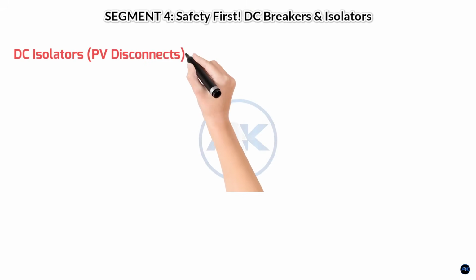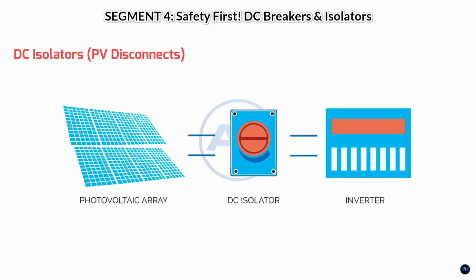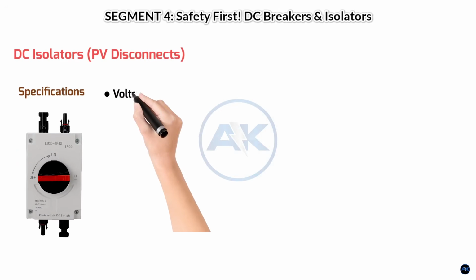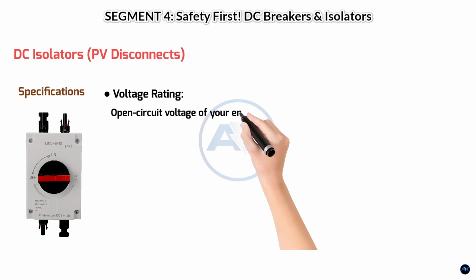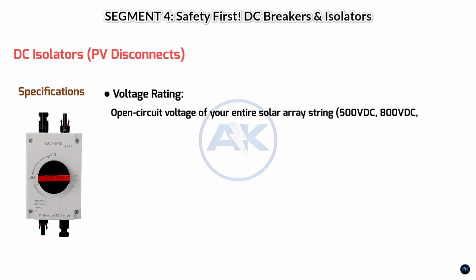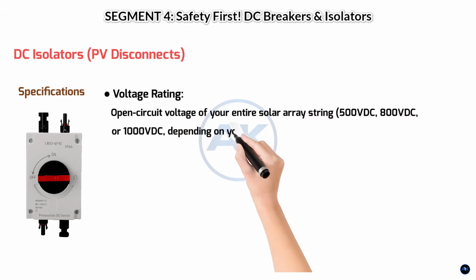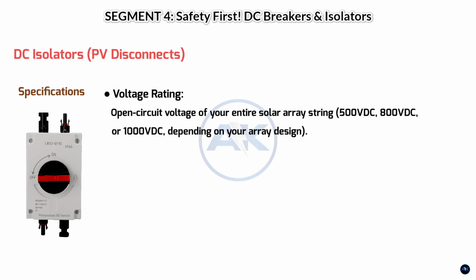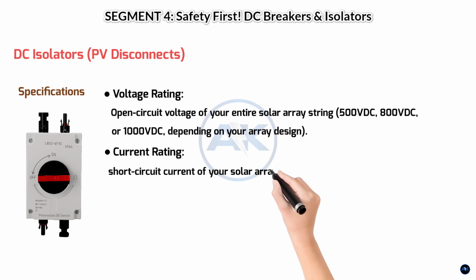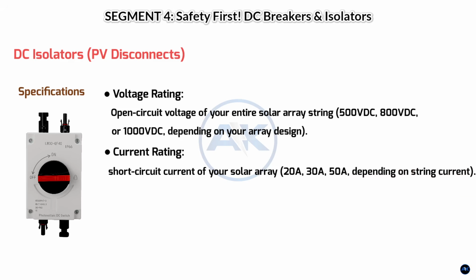DC isolators, PV disconnects. These devices allow you to safely disconnect the solar panels from the inverter. Placement: located between your solar panel array and the inverter's PV input, often found in a DC combiner box. Specifications. Voltage rating: must be rated for the maximum open circuit voltage of your entire solar array string, 500 volts DC, 800 volts DC, or 1000 volts DC, depending on your array design. Current rating: must be rated for the maximum short circuit current of your solar array, 20 amps, 30 amps, 50 amps, depending on string current.